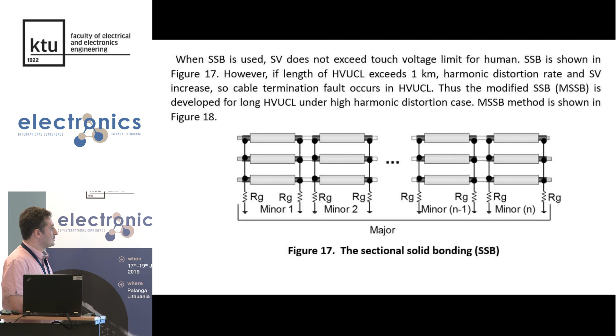In this paper, MSSB method is shown in figure 18. This is method for cable bonding, modified sectional bonding, MSSB. In MSSB, total line length is called as major part, and major part consists of minor parts. Minor part parameters are minor part length, distance between phases, grounding resistance, grounding inductance. These parameters should be optimized to obtain most economical and technical results. However, SV should be known to make optimization of MSSB.